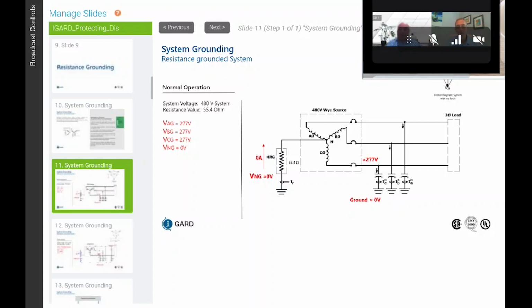The charging current is the current that goes from A phase through the capacitance to ground, through ground to all the other distributed capacitance that are on B phase or C phase and return back to the source. That's the only way they can return back to their source. But this ground, I've shown it here as a single point to ground symbol. In fact, this ground goes through your entire factory, your entire facility with the bonding network. These are all one ground. I hope that answers your question.